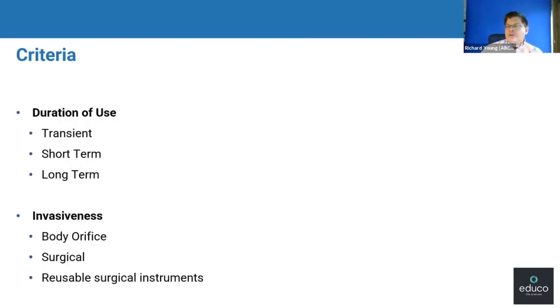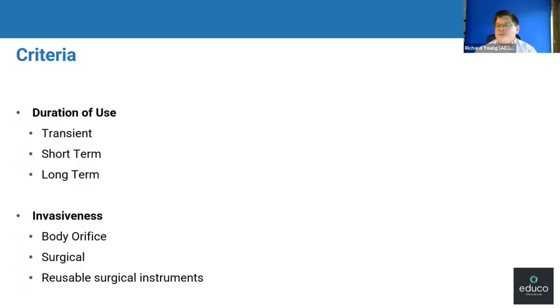Yeah, by all means. The first thing I'll say is that within any system, it's really important that an organisation, for each of their designs, sits down and does a formal thing called a classification rationale. It's a good discipline to get into, and it really forces you to look at the product, its design, its intended use and the intended users, and use that as part of going through the formal process of reviewing the classification rules that we're talking about.